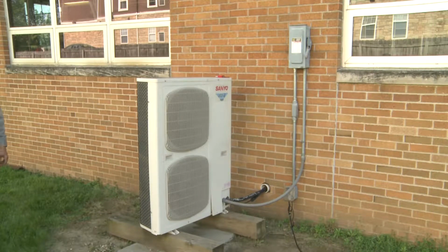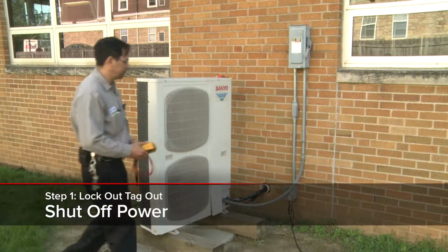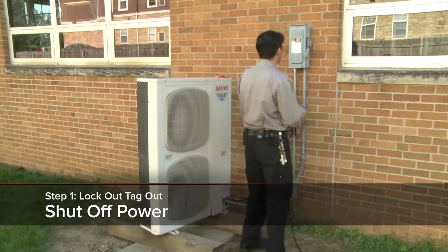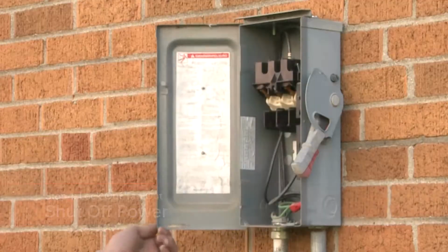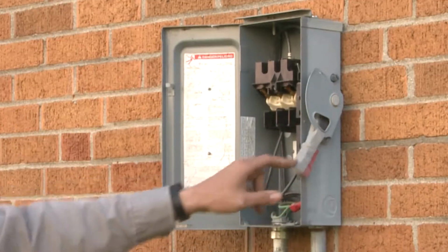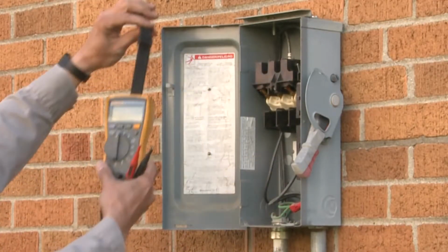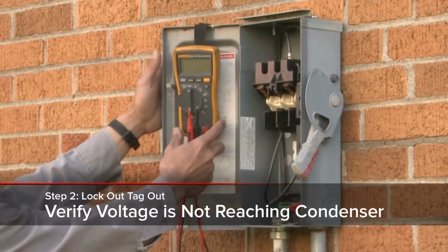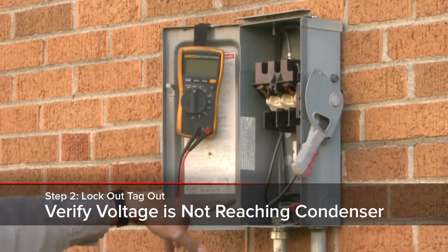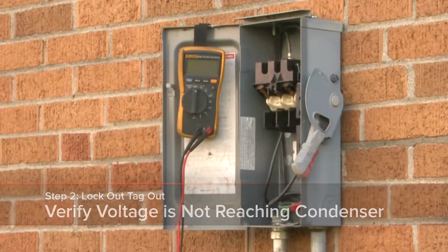equipment is de-energized, I'm going to verify that my voltage is completely disconnected from the equipment. So by doing that, I'm going to open this box right here, and obviously it's off right now, and I'm going to verify that my voltage coming from my line side is not going through the switch and going to my load side and energize the equipment.